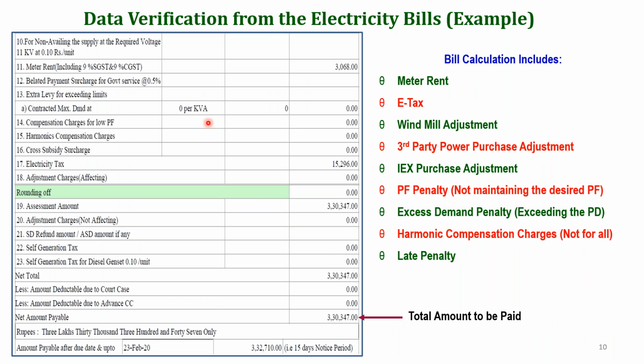Now the second page: the first page's remaining portion includes all the other parameters like the meter rent, and the belated payment charges. If you are exceeding the demand, the excess demand charges are also paid; that column is available. Compensation charges for low power factor penalty are also indicated here. I will show you some slides which have a higher penalty for EDC as well as low power factor. In Tamil Nadu, we do not have any harmonic charges for 11 kV and 22 kV consumers, whereas it is applicable only for 33 kV consumers, and soon it will come to other consumers also. So relate this information to your particular state and check it.